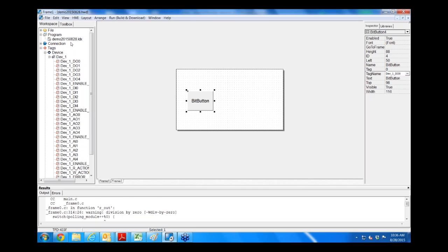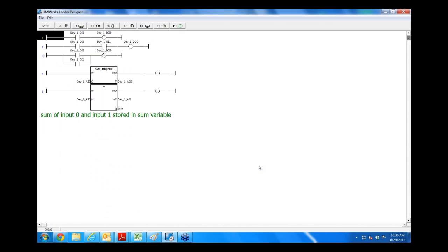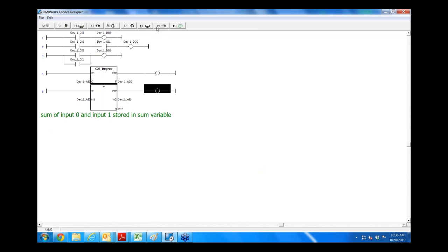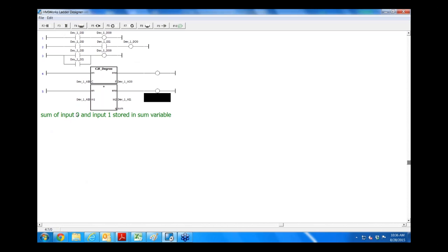A subroutine? Using the jump feature, is that right? He said, no, just in ladder logic. He just wants an example of the subroutine. Within ladder logic, the logic just keeps continuously going back and forth, starting from top to bottom. So there's no true subroutine. When you get into subroutines, you stand the chance of getting into loops. You can use the jump command to reimplement certain parts of the logic and then you can use the second jump command to jump out of it based on another condition. But traditionally, the ladder goes from top to bottom and it's just a continuous loop. Does that answer your question? He said okay.